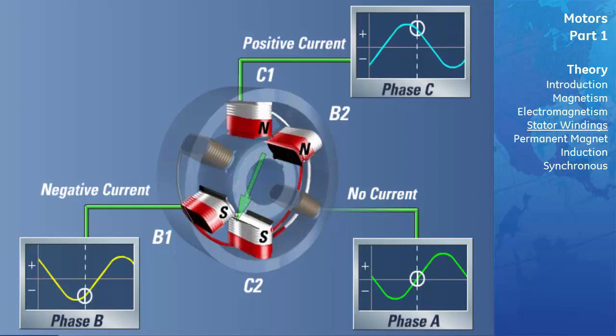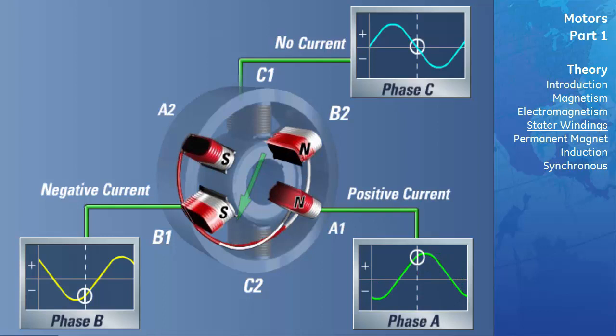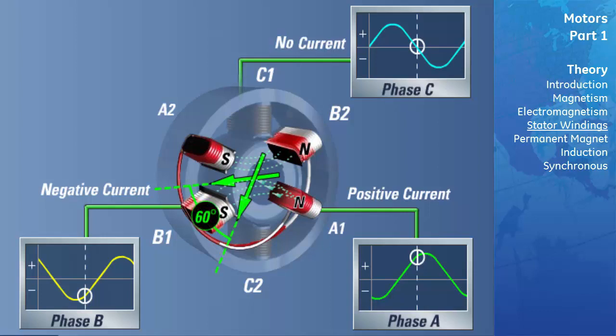The resultant vector shown is the vector sum of the magnetic fields formed between the C and B poles. If we repeat this evaluation 60 degrees later, phase C will have zero current flow. Phase B has current flow in the negative direction, and phase A has current flow in the positive direction. With reference to our convention, A1 and B2 will be north poles, while A2 and B1 will be south poles. The magnetic lines of flux will leave at the north pole of A1 and enter the nearest south pole at B1, and also leave B2 and enter the nearest south pole at A2. The resultant vector sum of the magnetic fields is shown here.